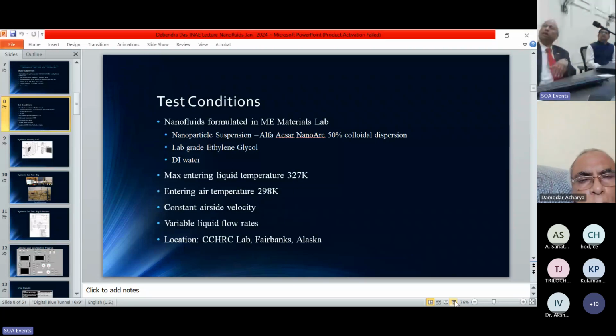We selected a maximum entering liquid temperature of 327 Kelvin and entering air temperature of 298 Kelvin—realistic temperatures recommended by heating coil manufacturers for cold regions. We varied the liquid flow rate, circulating it at various Reynolds numbers, and evaluated how much heat was transferred to air and what heat transfer coefficient was created in the coil.